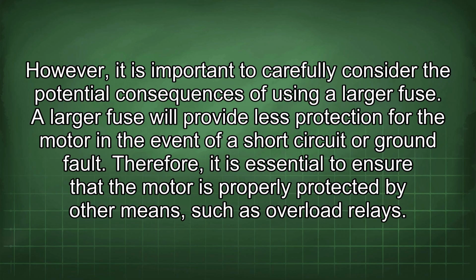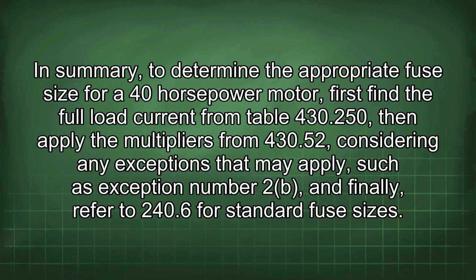A larger fuse will provide less protection for the motor in the event of a short circuit or ground fault. Therefore, it is essential to ensure that the motor is properly protected by other means such as overload relays. In summary, to determine the appropriate fuse size for a 40 horsepower motor, first find the full load current from table 430.250, then apply the multipliers from 430.52, considering any exceptions that may apply, such as exception number 2, and finally refer to 240.6 for standard fuse sizes.